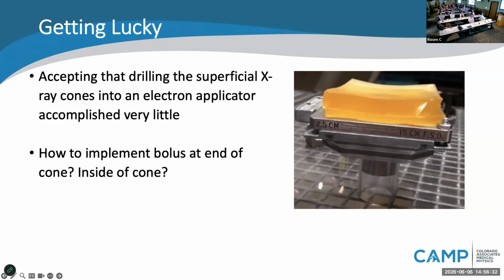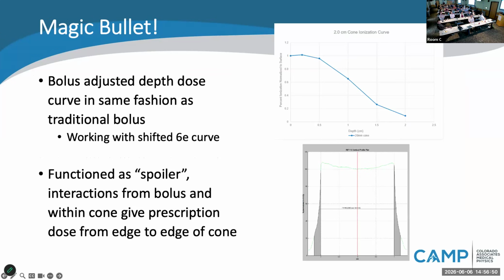So that's that 2 centimeter, rather 2.5 centimeter applicator that's been drilled into the 6x6 cone, and there's just 1.5 centimeters of bolus that's just laid on top of it. So I figured I might as well start there and see what happens. And it ended up doing the trick. So at the end of the day, we just got super lucky. The bolus that we put on top essentially just did what you would expect it to do. It shifted that 6E electron curve. So that's that graph at the top right there. That's our 2 centimeter cone ionization curve.